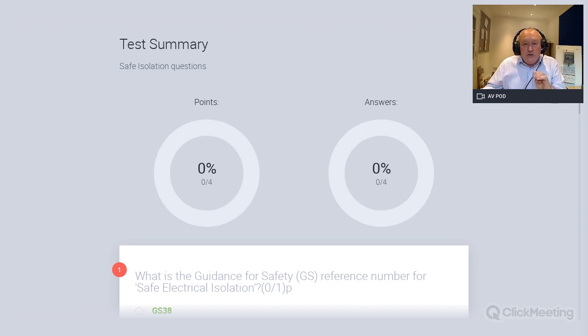Identify the function of a proving unit: it just proves that your voltage tester is working. That's all it proves. It doesn't prove the main supply or anything like that. All it's doing is confirming your voltage indicator, your voltage tester, is actually working.